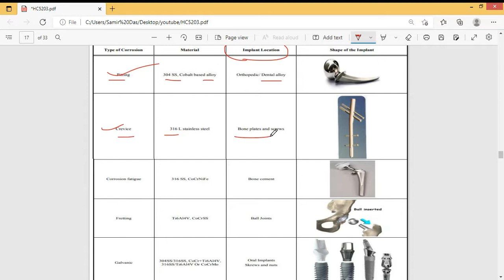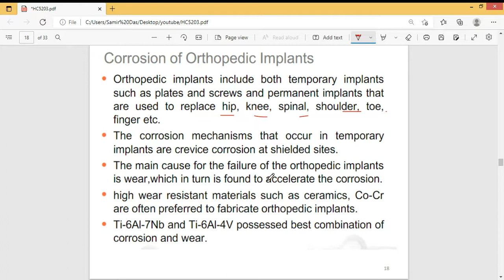Now we come to the corrosion of the orthopedic implant. In case of orthopedic implants, we use both temporary implants like plates and screws, and sometimes total prostheses, for hip, knee, spinal, shoulder, toe, etc. The corrosion mechanism that occurs in temporary implants is crevice corrosion at shielded sites. The main cause of failure of the orthopedic implant is wear, as I mentioned before. Wear always acts as a catalyst in case of corrosion.